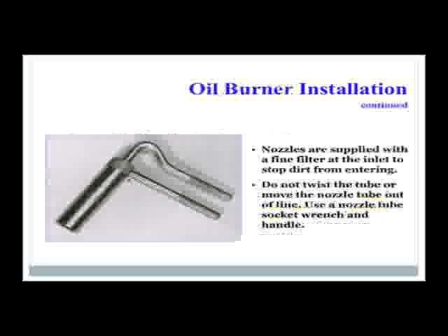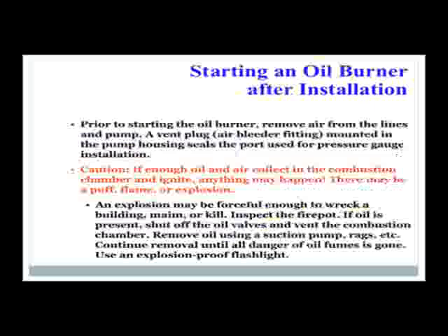Nozzles are supplied with a filter element at the inlet to stop dirt from entering. Do not twist the tube or move the nozzle out of line. Use a nozzle tube socket wrench and handle. Prior to starting the oil burner, remove the air from the lines and pump. A vent plug or an air bleed fitting is mounted in the pump housing, sealing the port that's used for the pressure gauge installation. If enough oil and air collect in the combustion chamber and ignite, anything may happen. There may be a puff, flame, or explosion. An explosion may be forceful enough to wreck a building, maim, or kill.